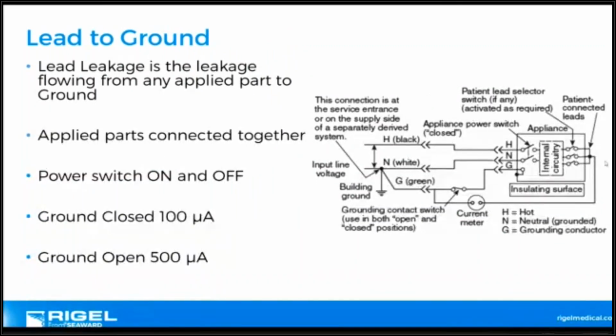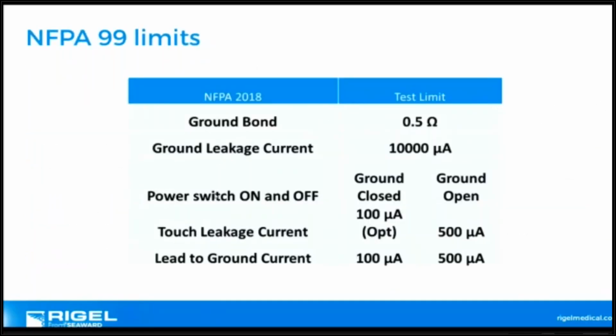Lead ground is your patient tests. It's almost identical to your 60601 patient lead testing, but note that all of the connections are shorted together as per 62353. So it's like a hybrid test. And then these are the limits for NFPA 99, the latest version being NFPA 99 2018. And we have various options for if you want to do ground closed and open, we have different pass-fail thresholds. Again, the 288 tester has all of these testing sequences built in. So although again, it's nice to have a good knowledge and keep informed in leakage currents, most safety analyzers will pick that up.